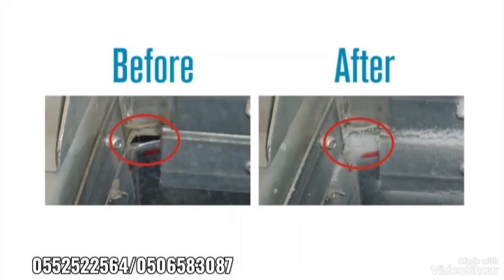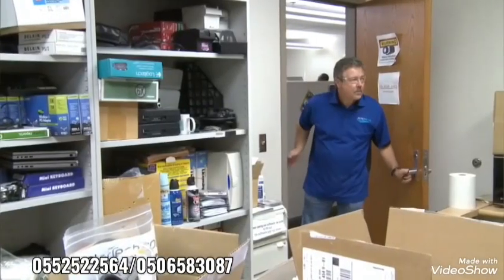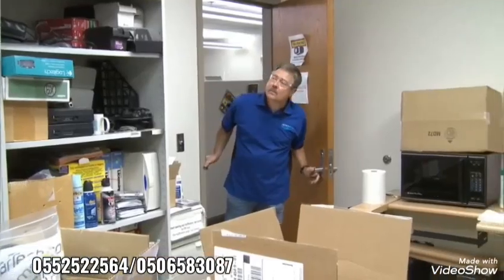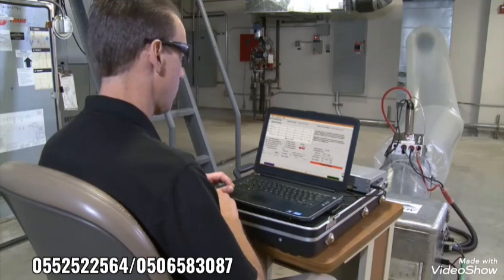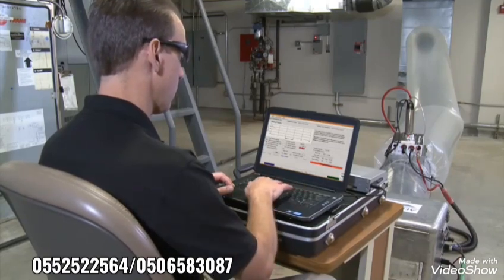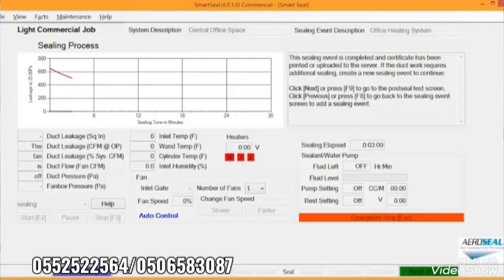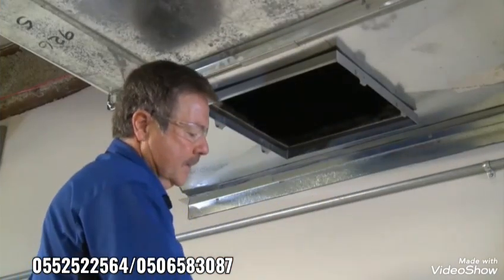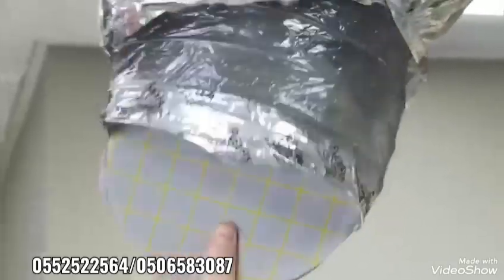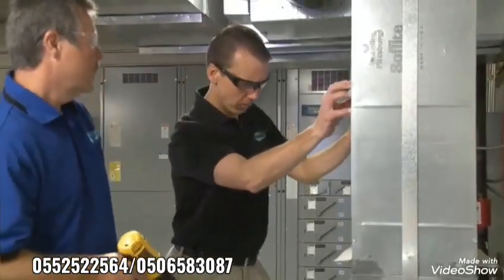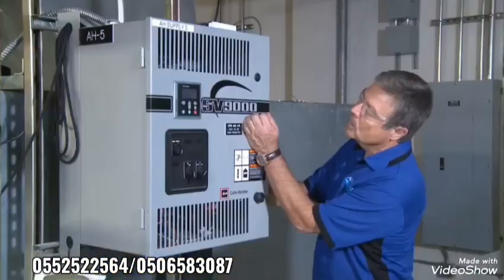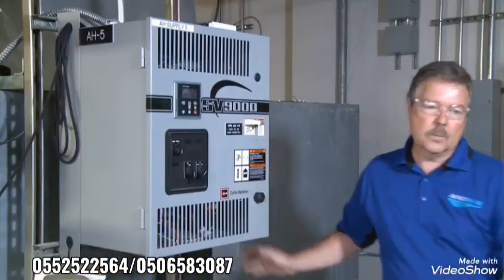As the sealant works inside the duct, the technicians will inspect the occupied space in the areas being sealed. During the sealing process, a live graph provides a real-time look at the progress. By monitoring the live leakage rate, the AeroSeal technician can determine when the sealing process has reached maximum results. Once sealing is complete, the technician removes the foam blocks from the system. All injection points are patched, the equipment is packed up, and the HVAC system is turned back on.